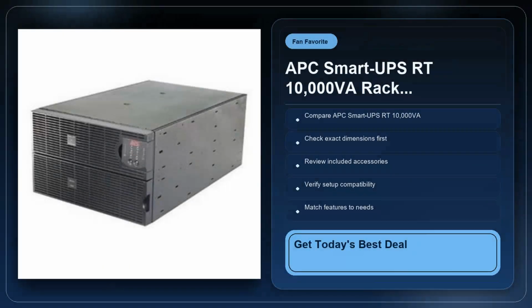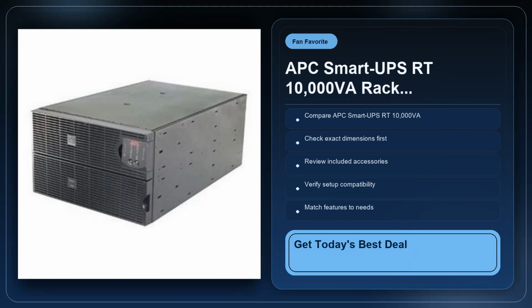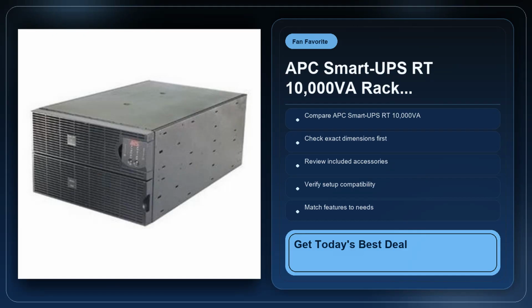Now, let's get into the practical strengths. One of the biggest wins is the 208-volt input. Most commercial data centers run 3-phase 208V, and the Smart-UPS RT matches that without needing a step-down transformer. That cuts down on wiring complexity and keeps power distribution losses low. The unit also integrates with APC's PowerChute network management card, giving you remote monitoring, automatic shutdown scripts, and email alerts. In practice, I've seen teams set up a simple SNMP poll that feeds straight into their existing monitoring dashboard, so they know the battery state of health before a power event even occurs.